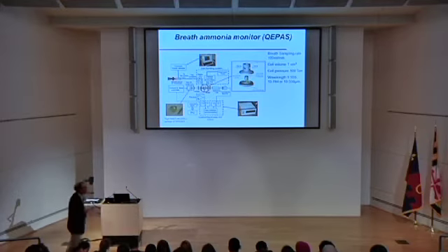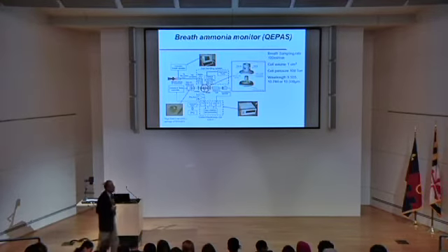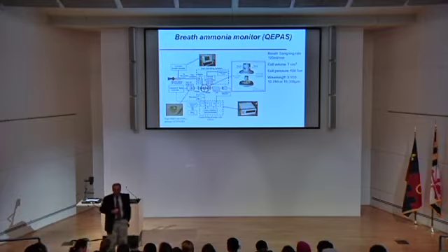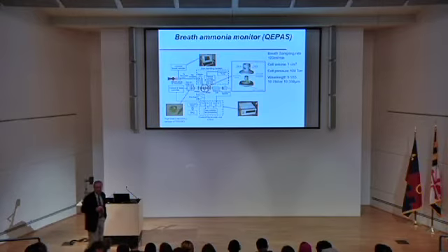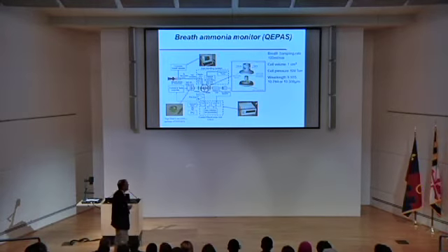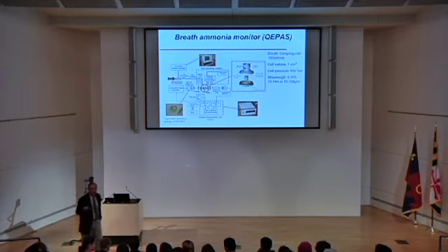This is a busy slide. This is an instrument that we built in collaboration with a group at Rice University, and we measure ammonia in real time using quartz-enhanced photoacoustic spectroscopy, QEPAS. We use a semiconductor laser in the mid-infrared to measure the photoacoustic effect of ammonia inside a cell, and the detector is the tuning fork of a watch.